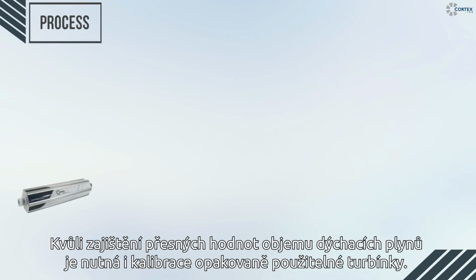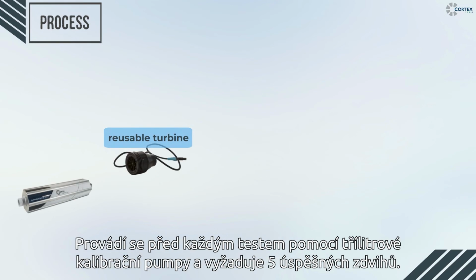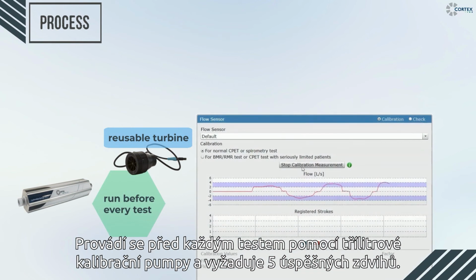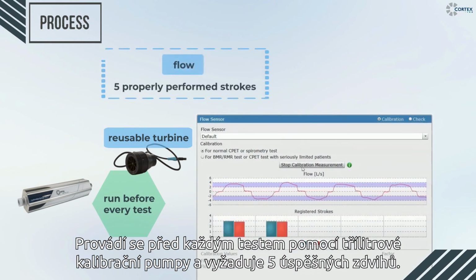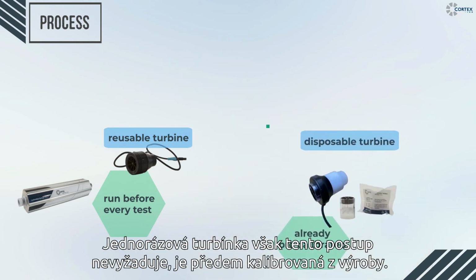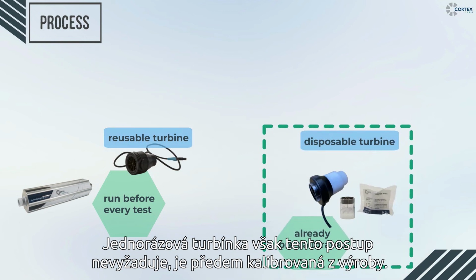Moreover, the calibration of the reusable turbine is mandatory to ensure accurate flow volume data. It is performed before every test and with the help of a 3-liter calibration pump. 5 successful strokes need to be completed. But this is not necessary when using a disposable turbine since they are pre-calibrated during manufacturing.